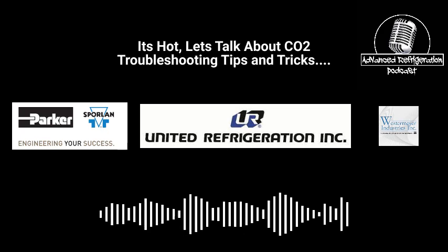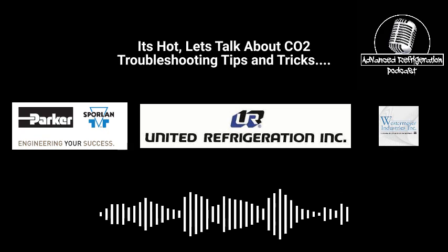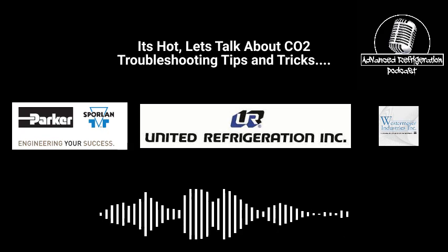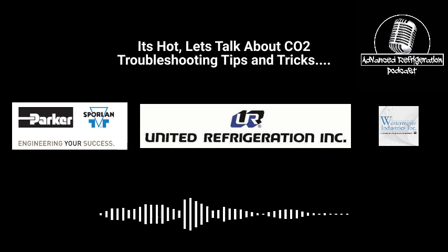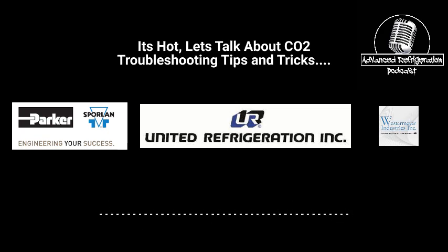Okay. So I thought if you'd be able to just settle everything down, just get everything pumped down where it doesn't even have the case load to worry about and just worries about the medium temp load. The problem with that is you're putting all the load in the tank. They can't handle the load. Gotcha. That makes sense. If you could shut some circuits down, then that would probably help take some load off of it, or shut the low temp off, take some load off of it.